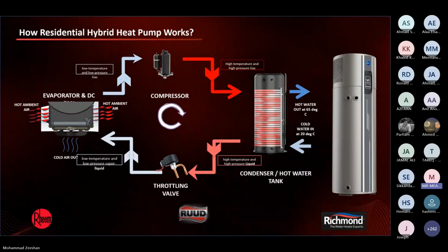So how does that work? We have evaporators, compressors, condensers, and throttling valves. The evaporator basically absorbs the energy from the ambient air and gives it to the refrigerant. This makes the energy of the refrigerant go up, which in turn increases its pressure slightly, changes its state, and slightly changes its temperature. The refrigerant then goes to the compressor, which is the heart of the system. Its job is to pump, basically taking the energy from the air and increasing its pressure and temperature.